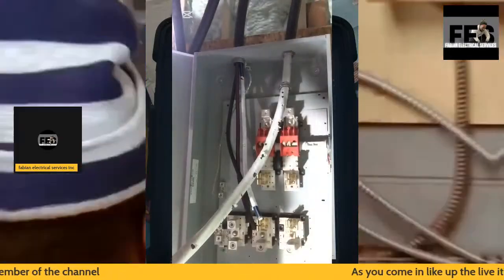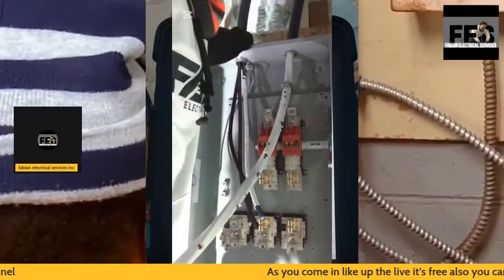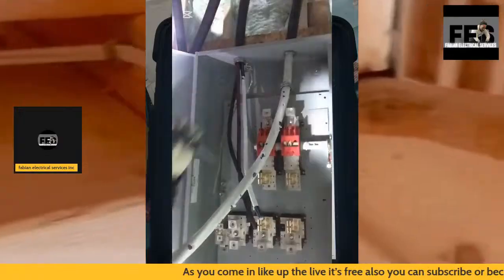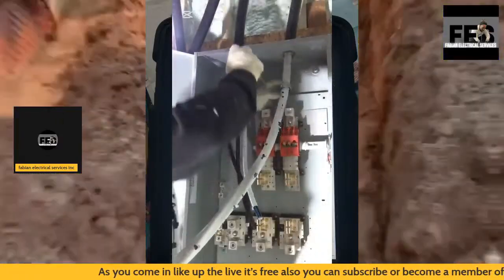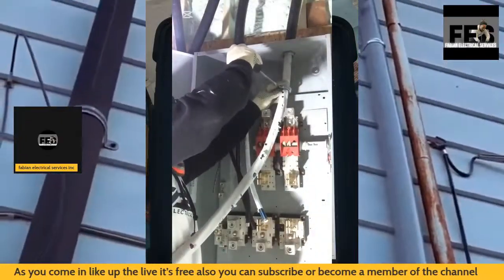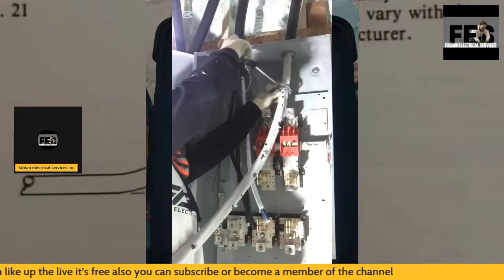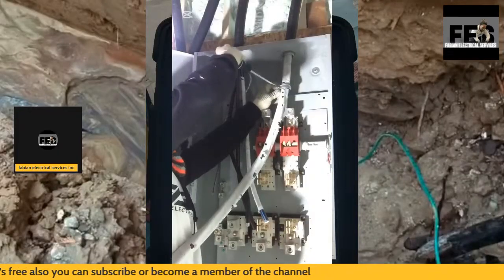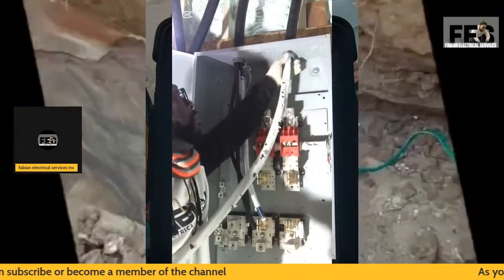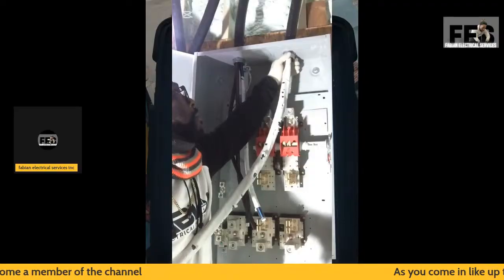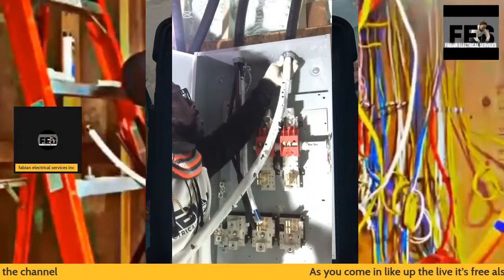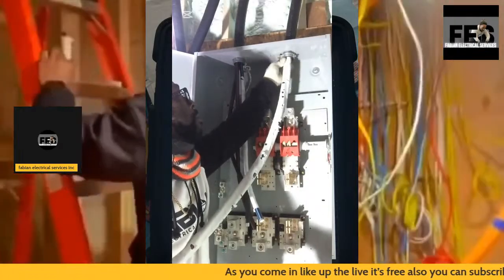On the left hand side, you're going to see the other installation. You're going to see my wire is grounded off onto the ground bushing. It is in code compliance, it's a code rule that states that. It's inside the electrical code book where you would find it, you just have to search.